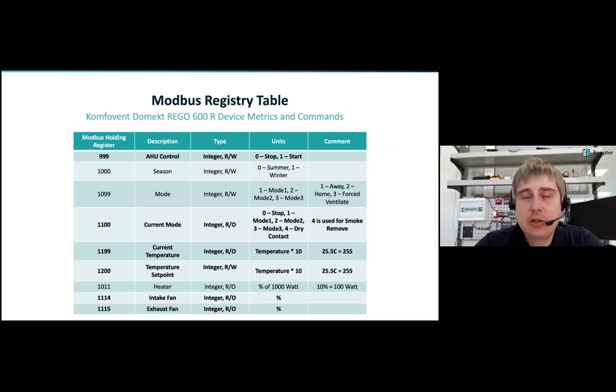After checking the documentation for the air handling unit, I prepared this Modbus register table, which has all Modbus registers which we will use in our integration. All of them are marked in bold, and they are just 6 registers. All of these registers are holding. This means they can be used for both the read and the write functions. However, the manufacturer specifically mentioned which can be used for the read-only operations and which can be used for read and write at the same time. Let's have a look at a few of them.